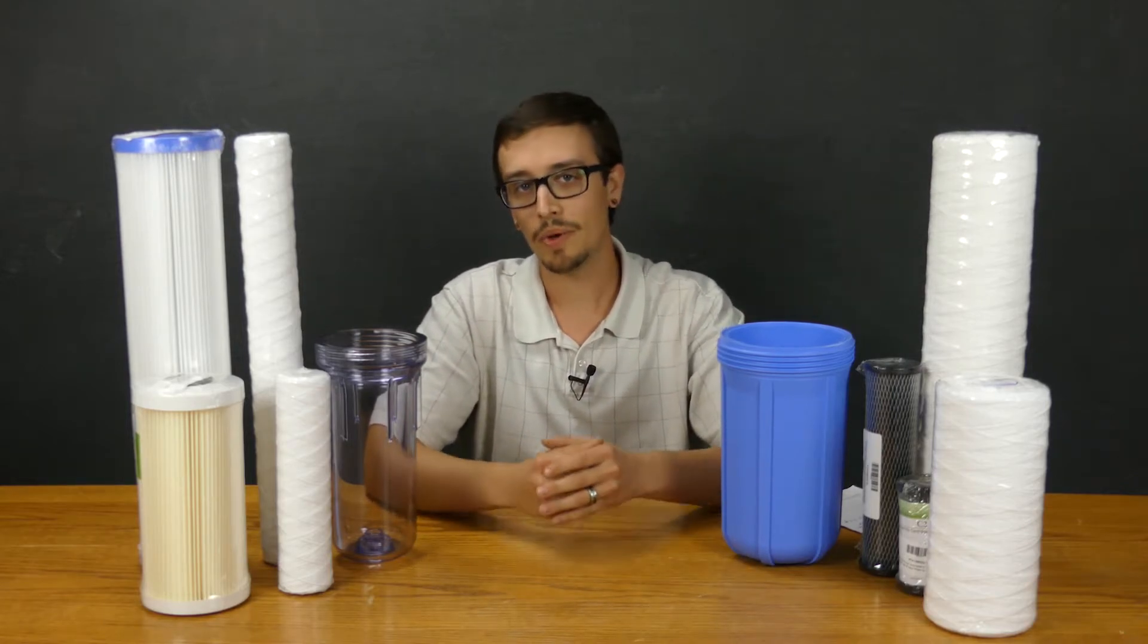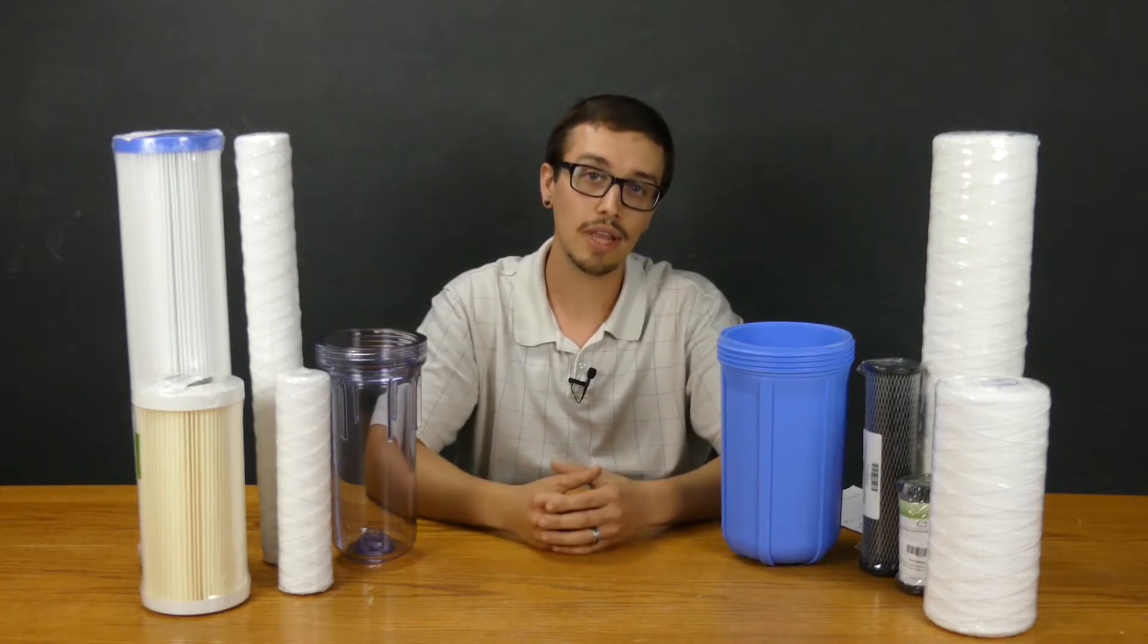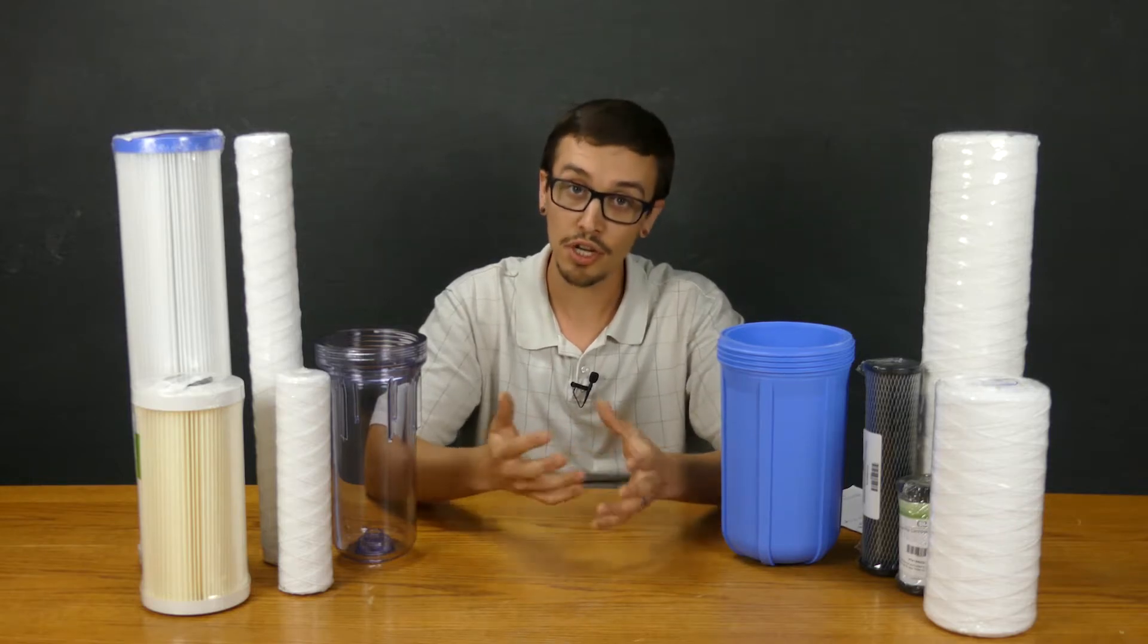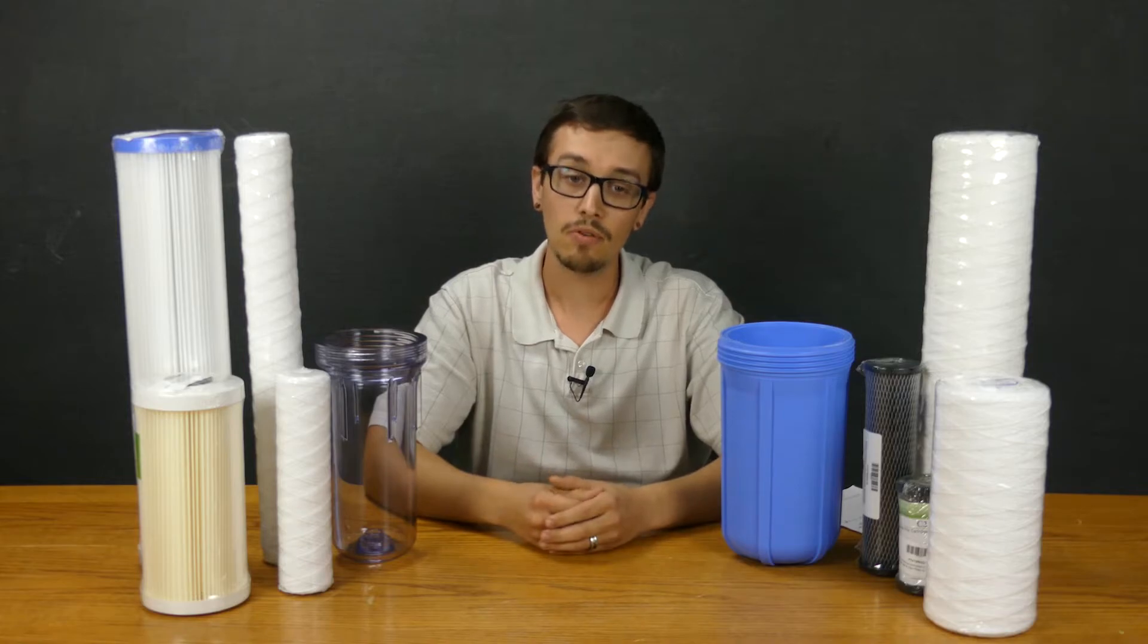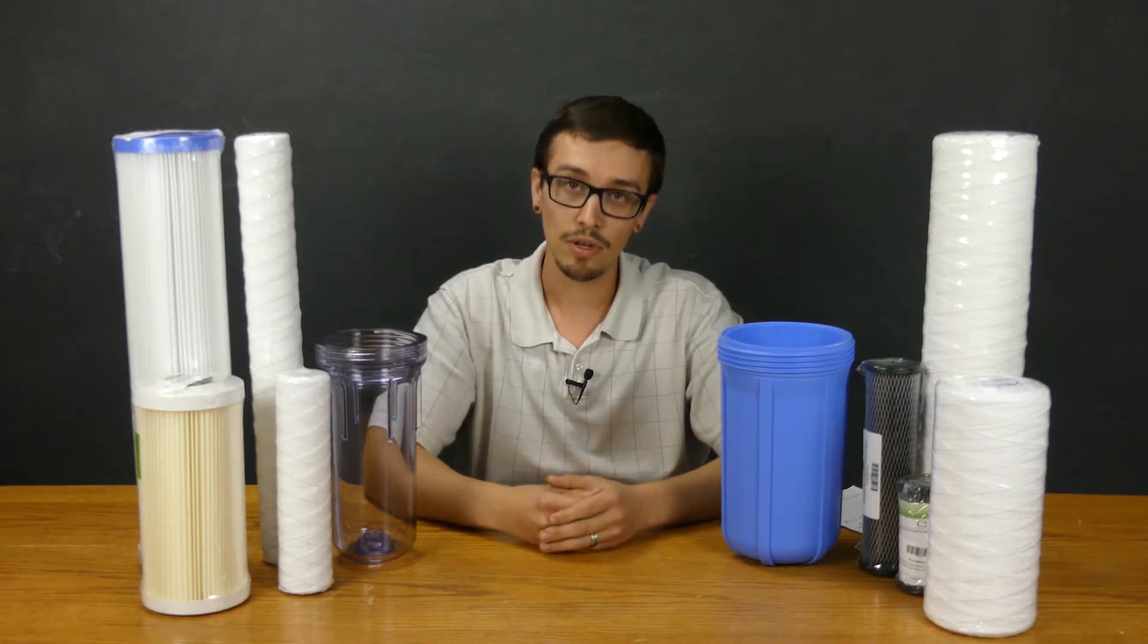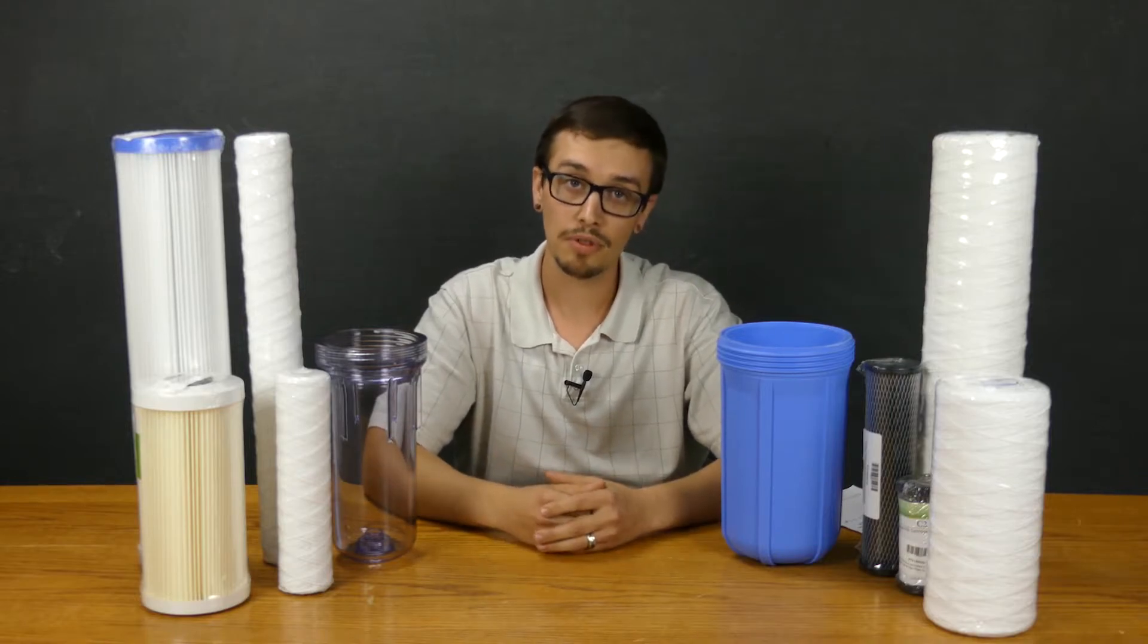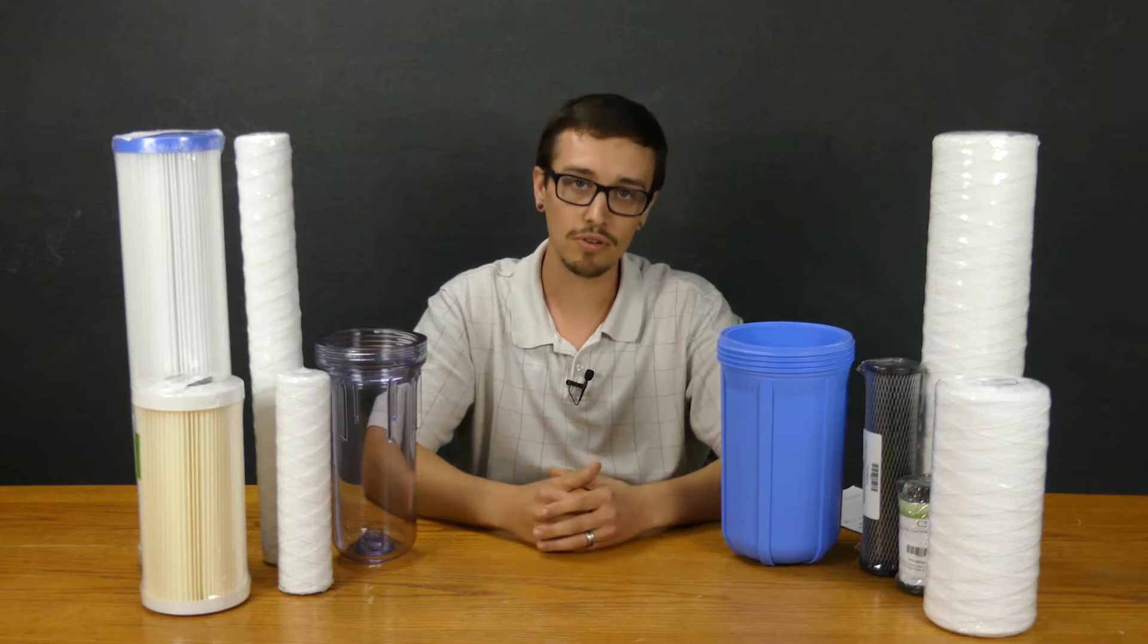By going with a larger filter, you're going to decrease the restriction on the system and also increase the length of time between having to change the filters. Even in the situation where maybe you've got a low flow but a lot of incoming sediment and debris, it might make sense to go with a larger filter just so that you're not having to replace and service that filter on a regular basis.